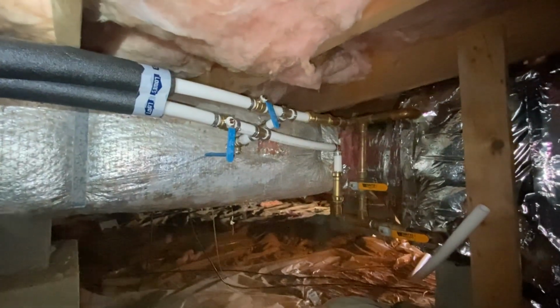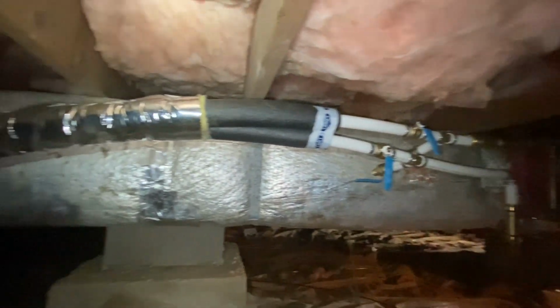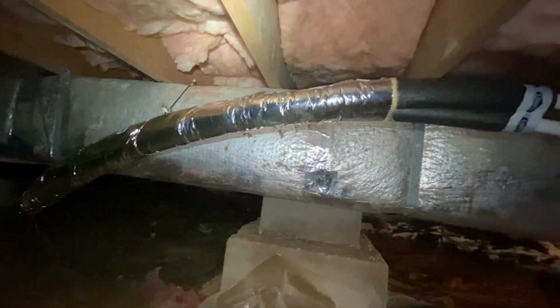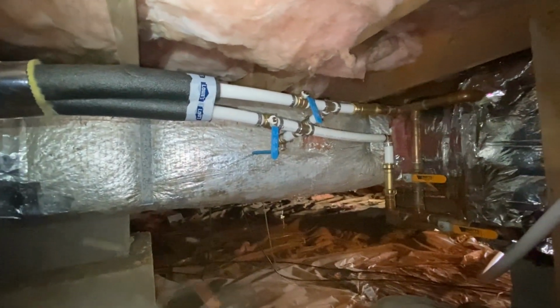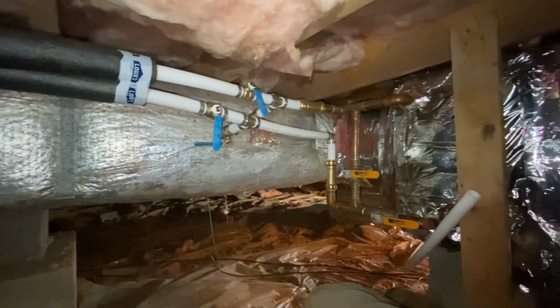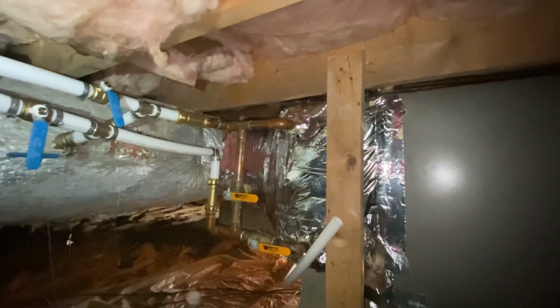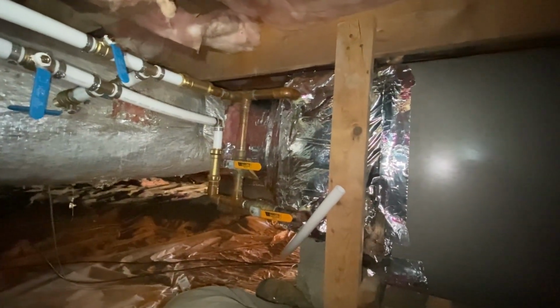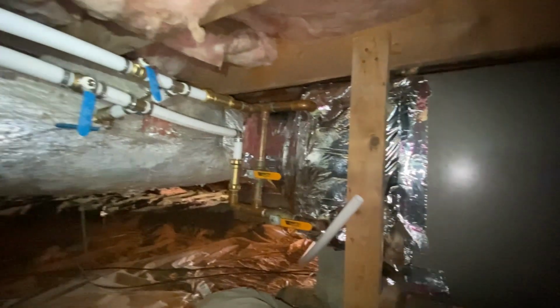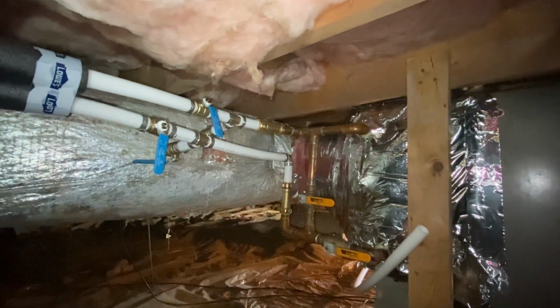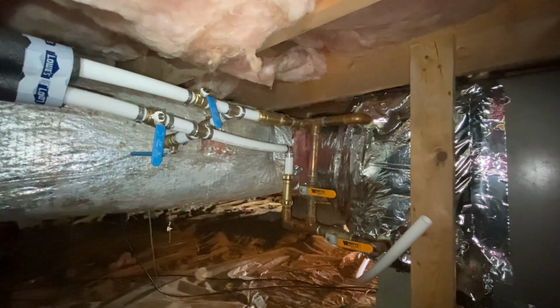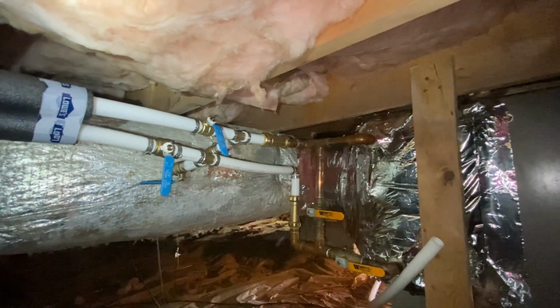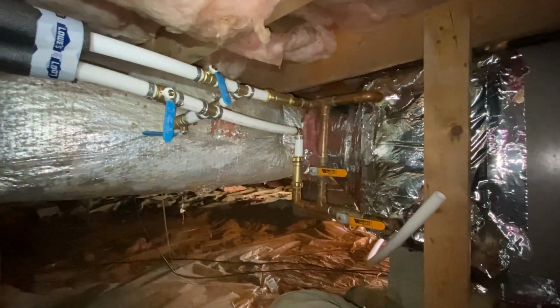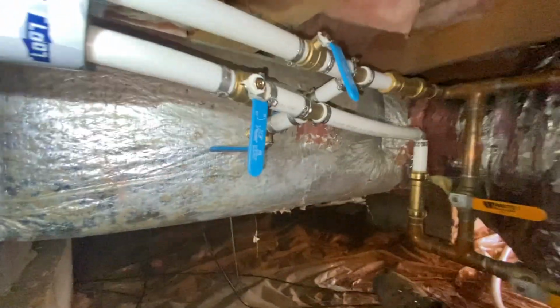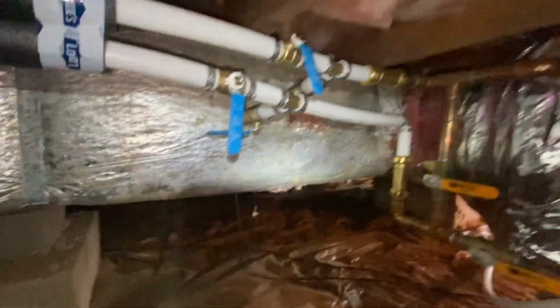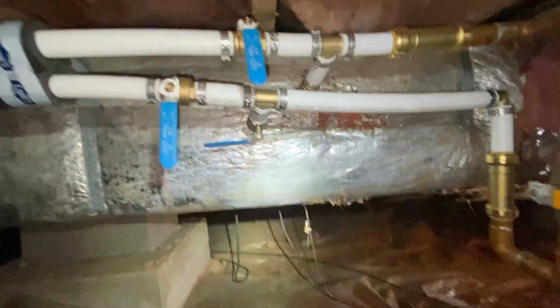So today is the day that I fit my pre-assembled, beautifully insulated under-house water supply from the outdoor wood furnace to my wonderfully solidly installed heat exchanger in the existing HVAC system. So there's one additional complication here that I would not have done, which is that the copper pipe that you see had already been fitted to the heat exchanger by a previous owner. But although it looks complicated, it isn't if you explain it step by step.